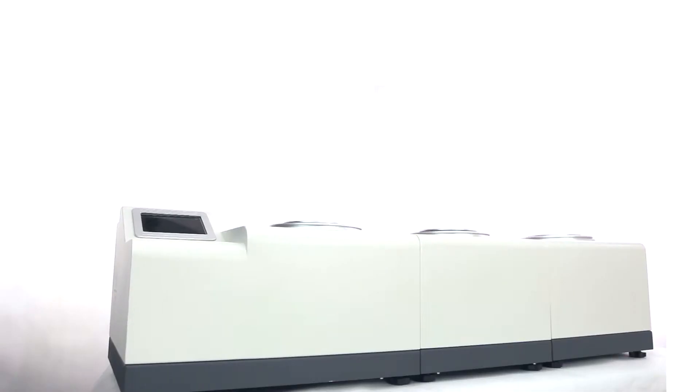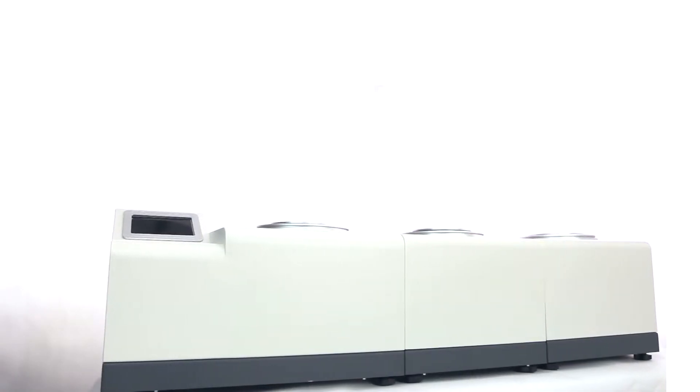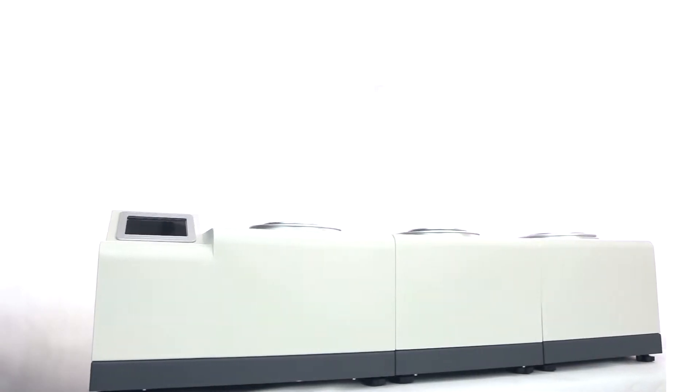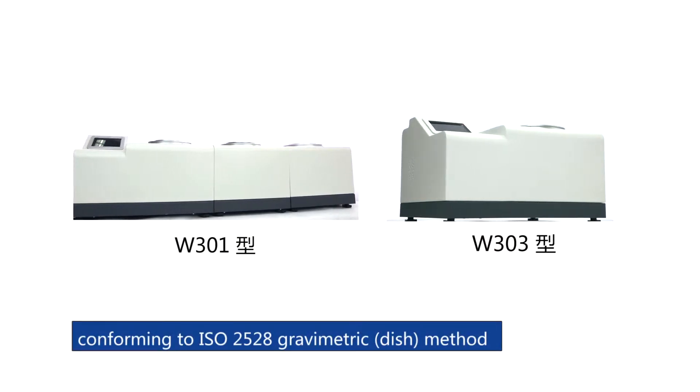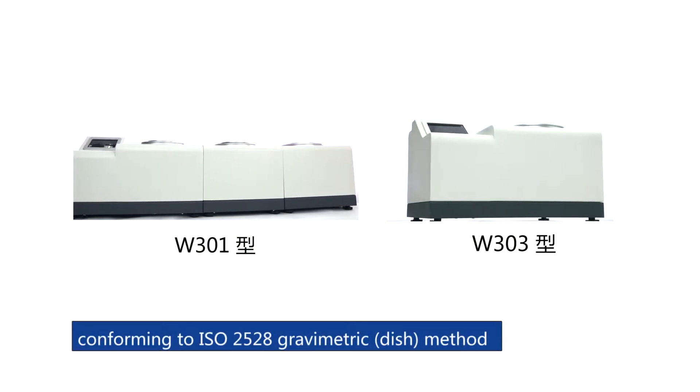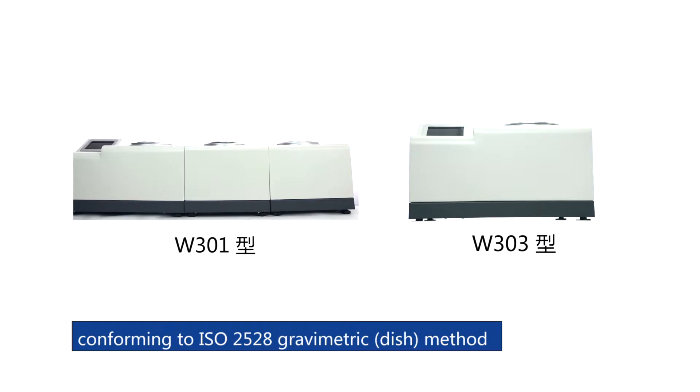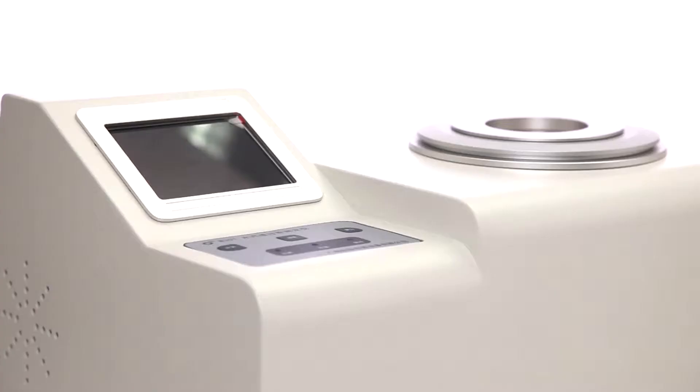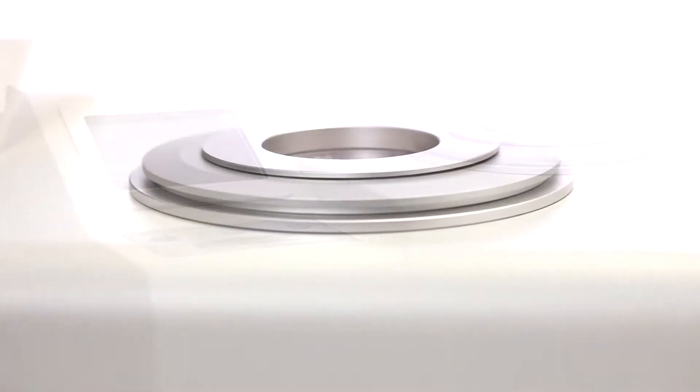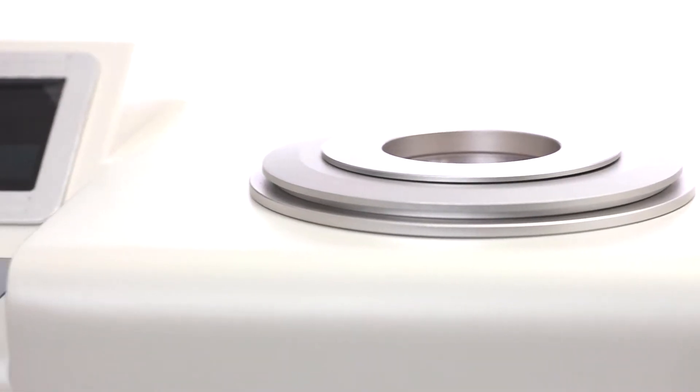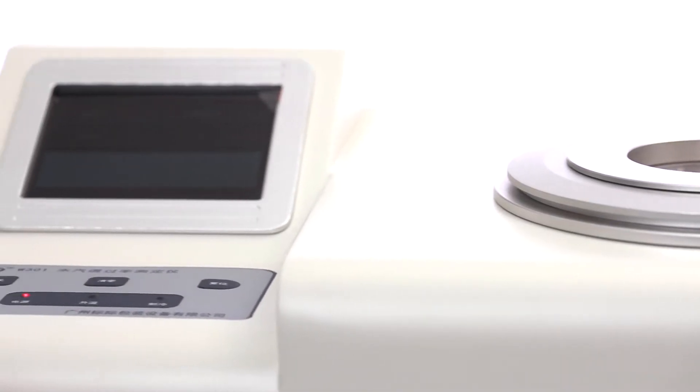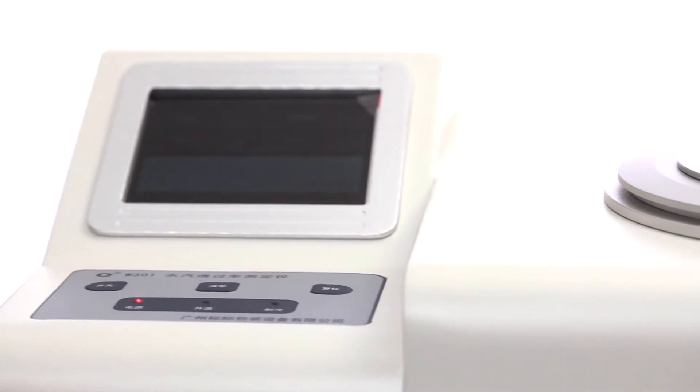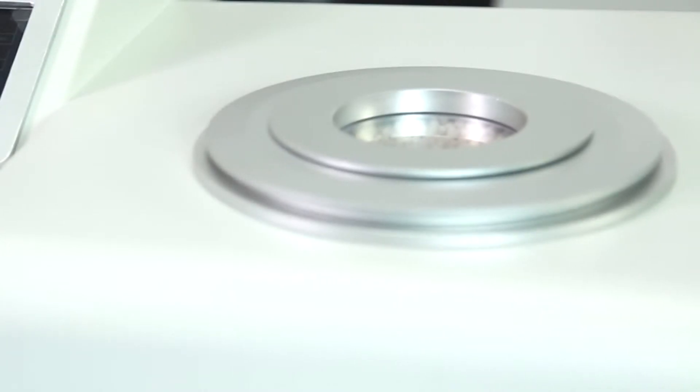W301 and W303 Water Vapor Permeability Analyzers are designed conforming to ISO 2528 gravimetric dish method. It is the gravimetric dish method water vapor permeability tester in China market that can test the transmission rate of high barrier materials such as aluminum foil.